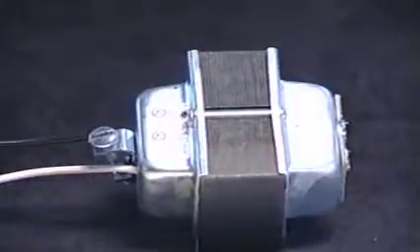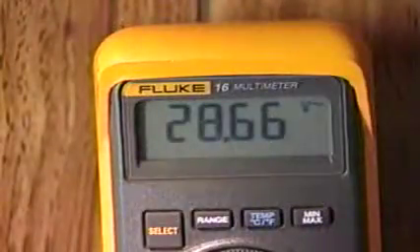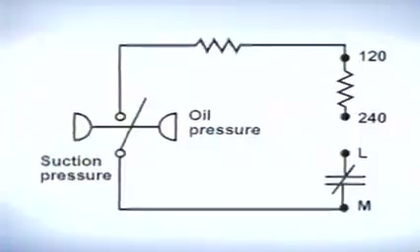Transformers provide the low voltage power source for many control circuits and can be field tested by taking voltage readings at both the primary and secondary windings. Thermostats open and close their contacts depending on the temperature they sense; they can be remote bulb or bimetal devices and are checked with a voltmeter. The voltage across an open set of contacts should be the same as the circuit voltage. Pressure switches open and close their contacts depending on system pressures. Humidistats maintain the desired level of humidity within an occupied space. Oil safety switches ensure that refrigeration systems operate with ample oil pressure.